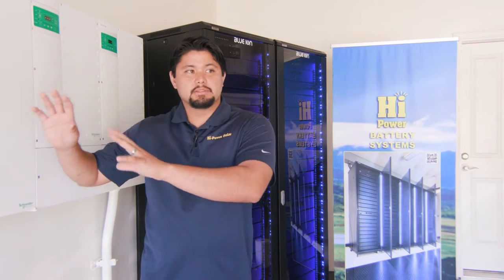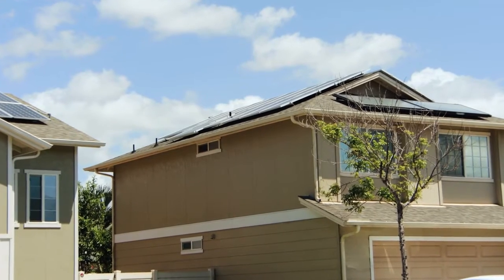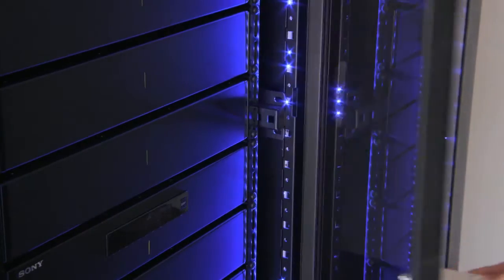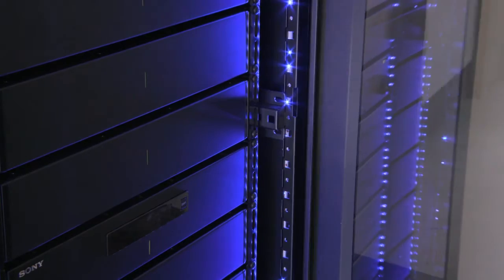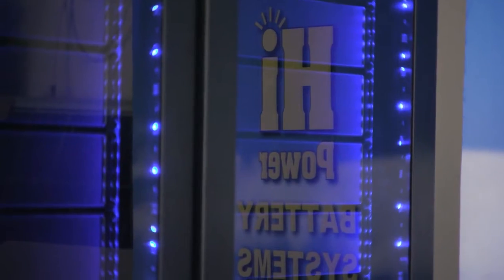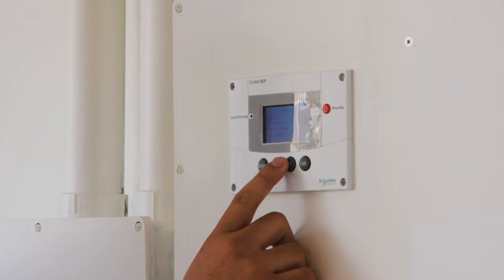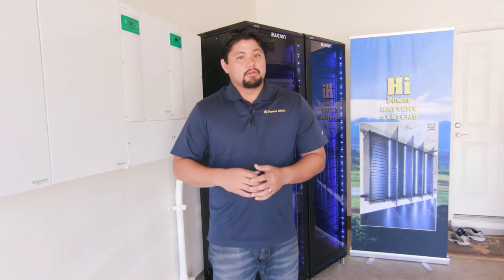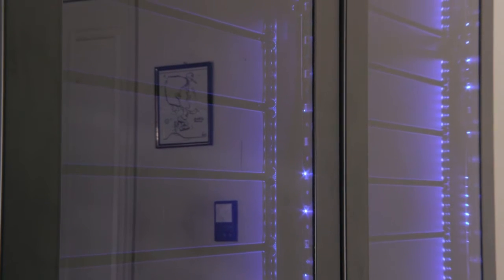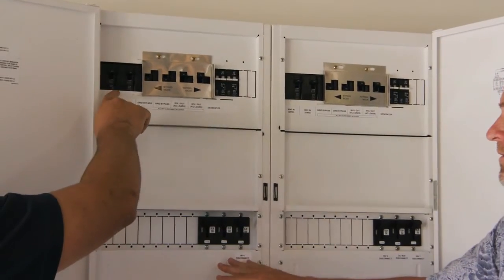This right here runs the whole house — right now it's running it from about 4 o'clock to 8 o'clock in the morning. We built this system to last 24 hours. The people here were running an $800 to $1,000 electric bill, and what we've done is essentially zeroed out their electric bill. The PV energizes their home in the daytime, and as soon as about 5 to 6 o'clock hits, the batteries kick on and run the home at night. So there's no power being pulled from HECO.